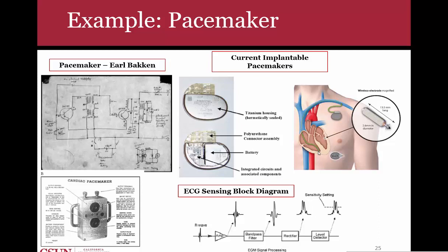At the very edge of this lead, there's going to be some electrodes for stimulation. Now, you can't just stimulate willy-nilly. You actually have to measure the ECG of the person. So within these leads, you also have an ECG sensor that measures the local ECGs in the heart.